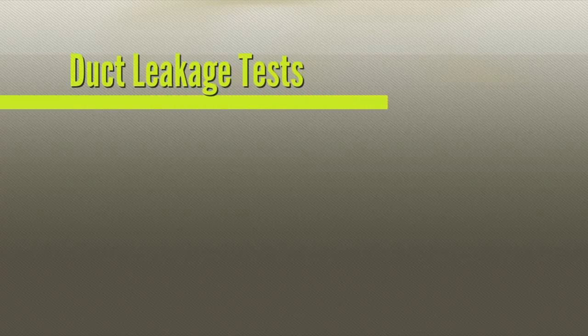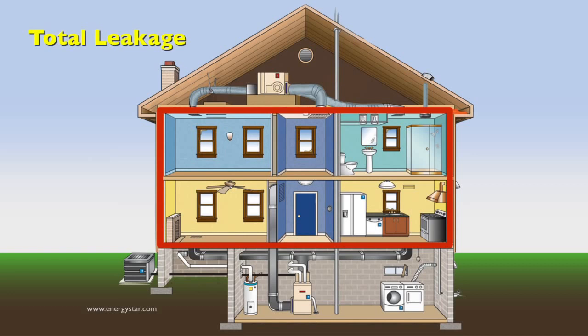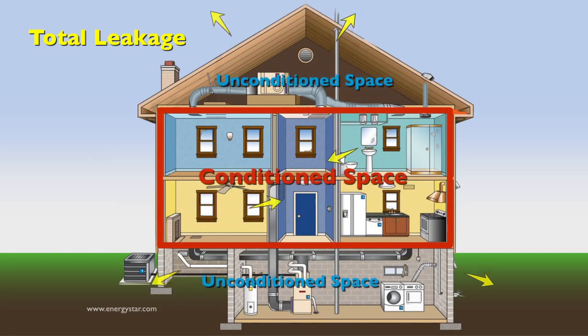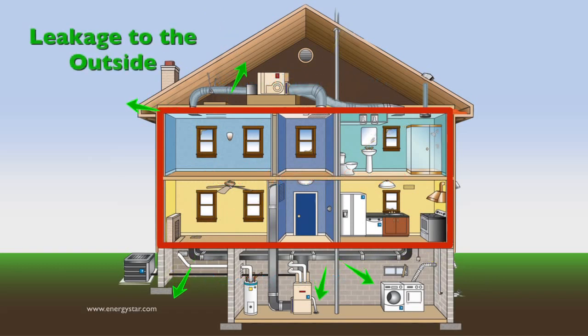There are two types of duct leakage tests: total leakage and leakage to the outside. Total leakage quantifies the total amount of conditioned air that leaves the duct system into both conditioned spaces, like living rooms, and unconditioned spaces, like attics, crawl spaces, and garages. Leakage to the outside quantifies only the amount of duct leakage leaving the building envelope. This duct leakage is lost into the unconditioned spaces where the ducts are located.